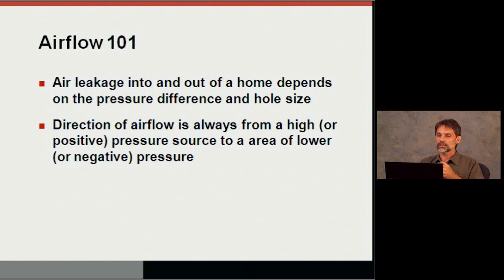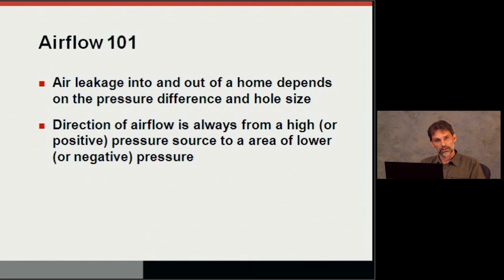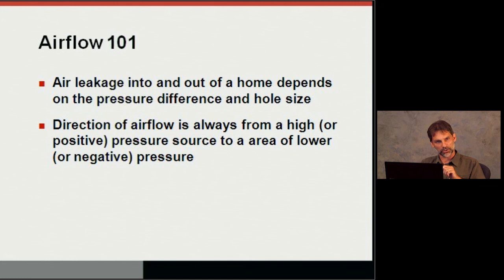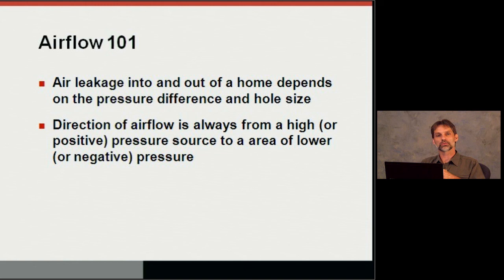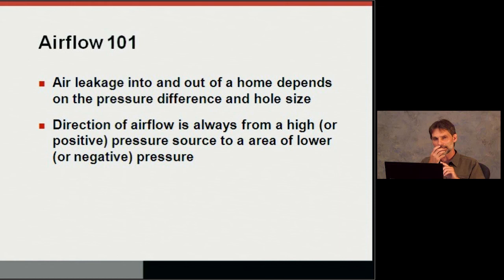Similarly for measuring exhaust fans — there's a simple box tool with an adjustable hole and a sensitive digital pressure manometer that measures static pressure in inches of water column or Pascals. We can go to quick charts to find the flow, or digital manometers can read out flow directly. It's all based on knowing the pressure difference across the hole and the size of the hole.